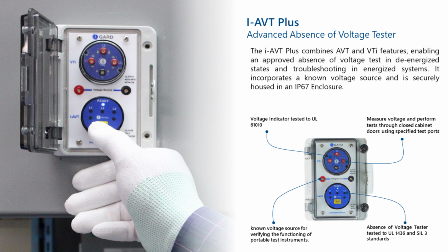This is in order to help people understand better what's happening with their system. The absence of voltage tester is used specifically to test for the absence of voltage. But the test port is used to measure voltage and for troubleshooting, all from outside of your cell. No longer do you need to go inside the cell to do troubleshooting. The voltage indicator is tested to UL 61010. You can measure voltage and perform tests, and again, you don't have to open the door. We also have a voltage source, so you can actually test your meter to see if it's working.